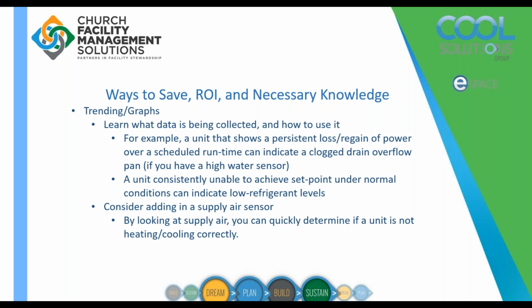We also see sometimes a unit that can get really, really close to set point, maybe 2 to 3 degrees off of it, but never quite get there no matter what. No matter if it's early morning, late afternoon, if the doors are open, if the doors are shut, it doesn't matter. If we start seeing that trend, especially if previous to that it was achieving set point, a lot of times that's a good indication that we need to check the refrigerant level. Low refrigerant will still provide some cooling, but it's just not going to be as efficient and as effective, and that's how we can tell, and we can look at that graph.